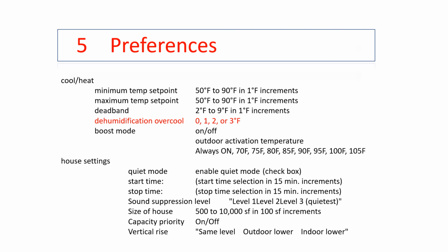Under house settings is where we're going to find our quiet mode. If you check the box, you can do a start and stop time. Let's say you want to run it at night. We have very little solar gain at night, so your house isn't as hot, so we might not need capacity, so we allow it to run to level 3. Keep in mind, when you run the fan and compressor that low, you can lose capacity. So if you do set to level 3 and you lose capacity, as long as your capacity priority is switched to the on position, it will ignore the call for quiet mode and go back to full capacity.